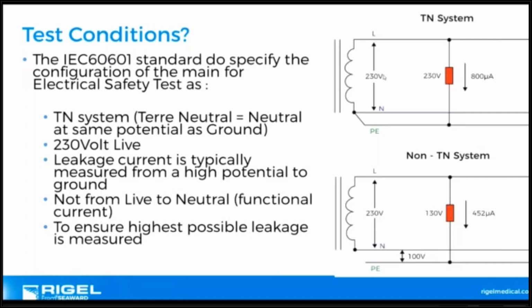Why? Because if I've got the current flowing through here, and protective neutral is common, if I've got 230 volts from live to neutral, I also have 230 volts between live and earth. Let's say this resistor is our medical device. This has got a fault current. This would be a failure. All the current would flow through the resistor, the medical device, and the protective earth from the live conductor.